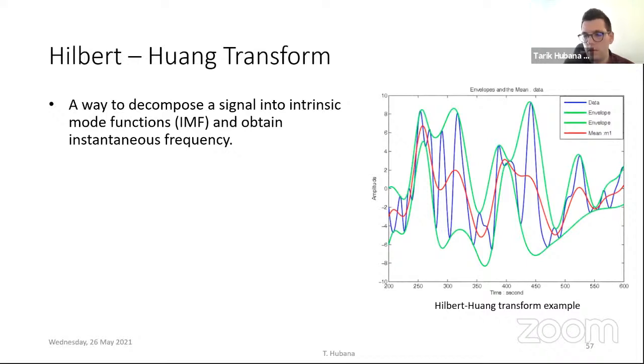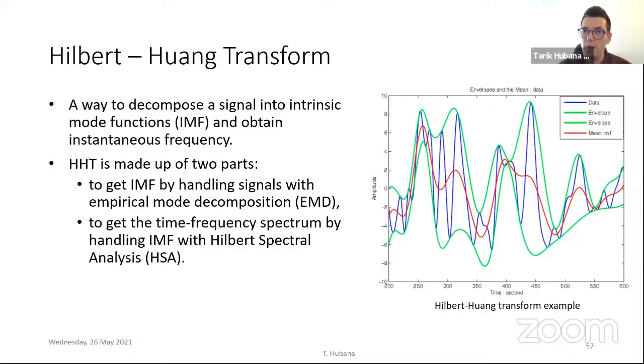One interesting approach that was used in this research is the Hilbert-Huang transform. We tried to use a Fourier transform, a fast Fourier transform, which is common for measuring harmonics, especially according to the EN 50160 standard here in Europe. But the time for measuring and calculating harmonics may be too long to use them efficiently in protection. So an interesting concept we tried is the Hilbert-Huang transform, which is, in short, a way to decompose a signal into intrinsic mode functions and obtain instantaneous frequency. It is made up of two parts. The first is to get the IMFs by handling signals with the EMD, empirical mode decomposition, and the second is to get the time-frequency spectrum by handling these IMFs with Hilbert spectral analysis.